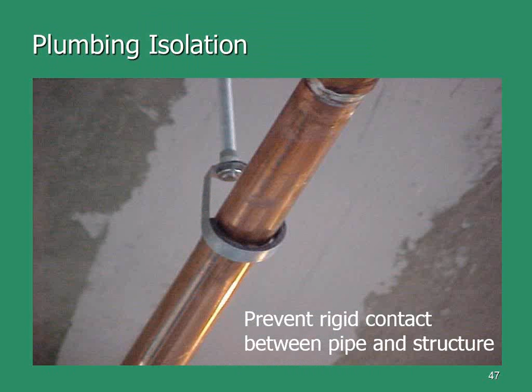The guys installing it put the springs in, then the lunch whistle blew. They came back an hour later and said, we just need to torque down the bolts here, it looks level, we don't even have to adjust it, and they walked away. As soon as we jacked that up and pulled those nuts out—I used to bring one of those to these tech talks, I'm traveling light today—as soon as we pulled those out and it went down and we leveled it a bit, the noise went away in the conference room.